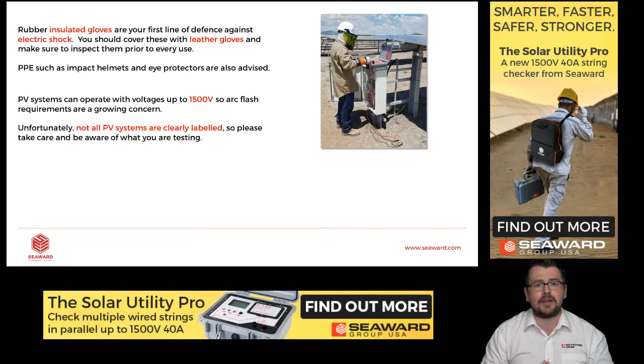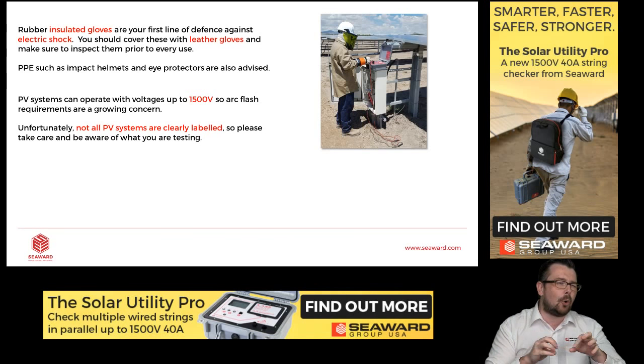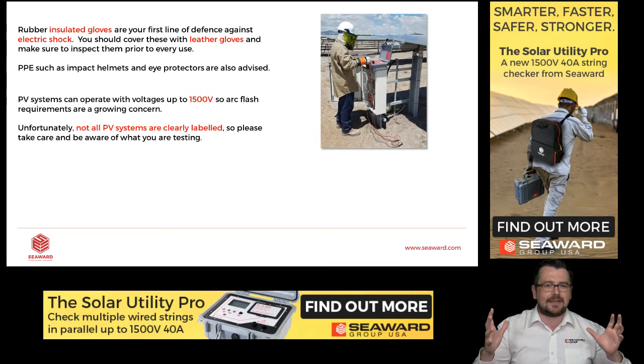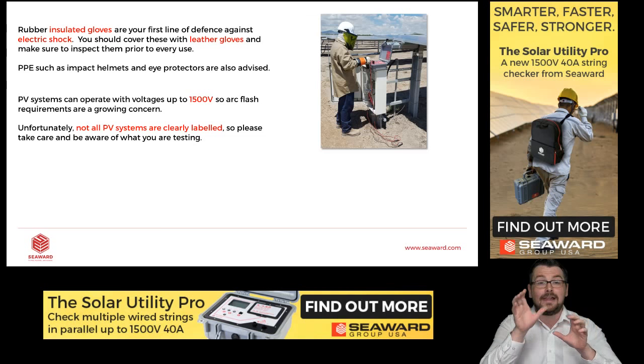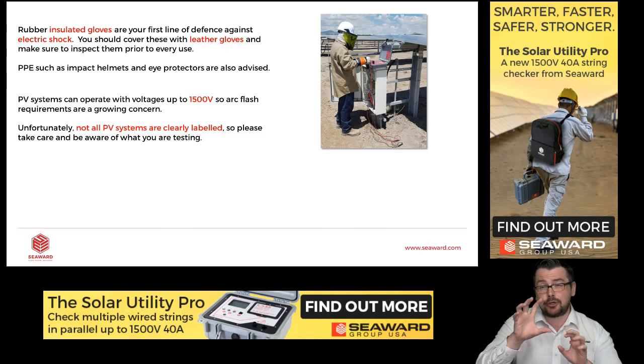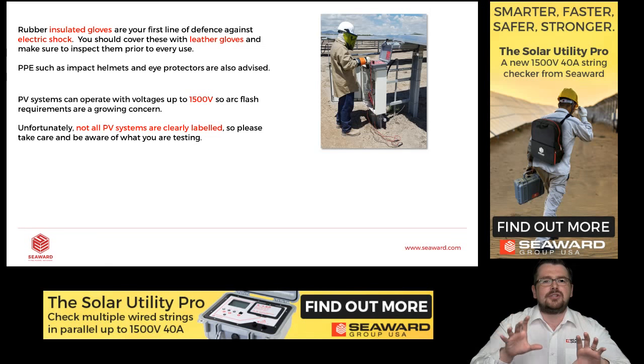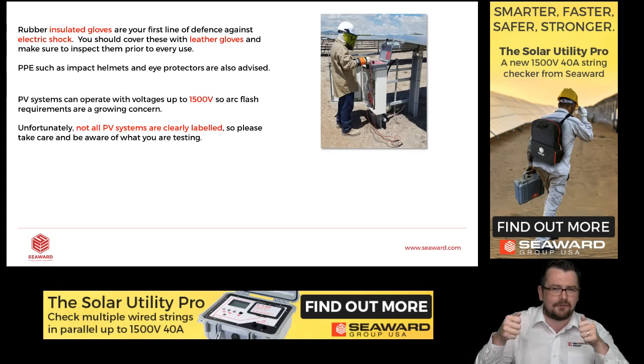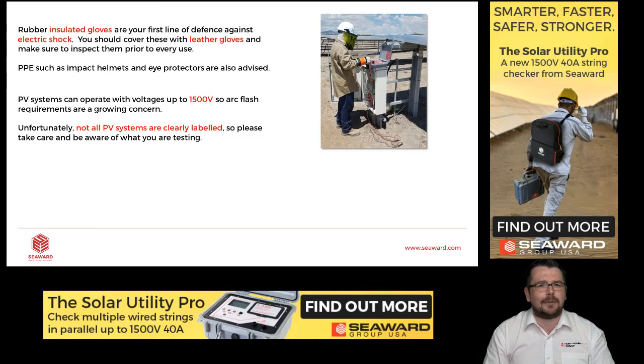PV systems can operate at a high of 1500 volts. So arc flash requirements are very much a growing concern. And unfortunately, not all systems are clearly labeled. So the point is that if you're on a new system, you probably know what you're dealing with. But if you're going back to a site to do some maintenance work, you might not know what the string length is, or what the history of the solar farm is, particularly if it's not very well labeled. So it's very, very important just to look at the panels, count the number of modules in the string, and try to understand what you're dealing with before you connect your tester. And we're going to cover that a little bit later on.